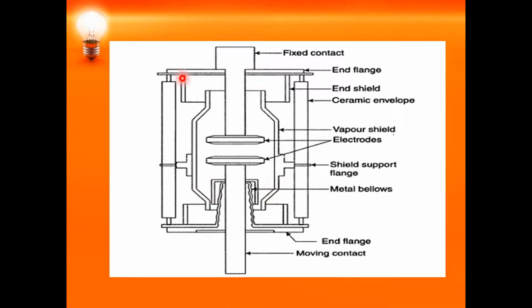You can observe how the vacuum circuit breaker looks. Like other circuit breakers, it has a fixed contact and a moving contact connected by the electrodes. It has a vapor shield, and inside this vapor shield the vacuum is maintained. That means the contacts are present in the vacuum, and there is a metallic bellow at the bottom. The function of this metallic bellow is to help the moving contact move up and down.